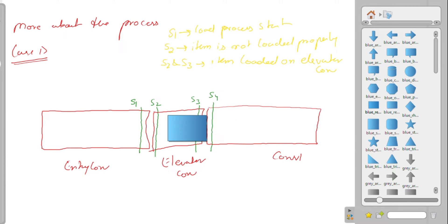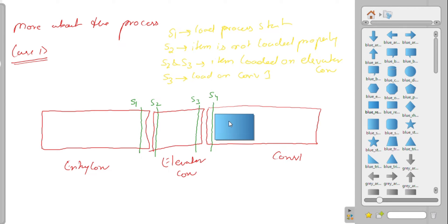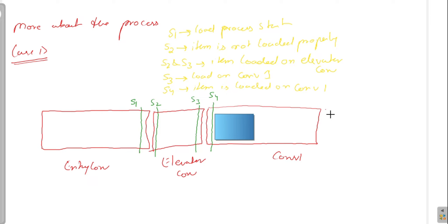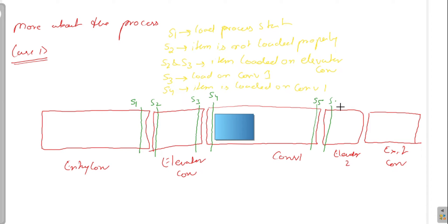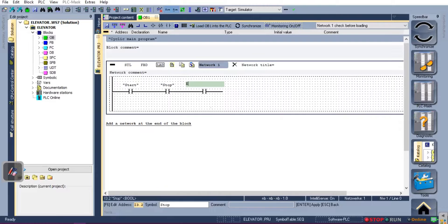As we need to load the item onto conveyor 0, the load actuator will stay on, meaning S3 and S4 sensors will both detect the item. For the time S3 is detecting the item, we need to keep the load actuator on so the item can be transferred to conveyor 0 properly. When the S4 sensor detects the box, we need to turn on the conveyor 0 actuator so that we can load the item on conveyor 0.